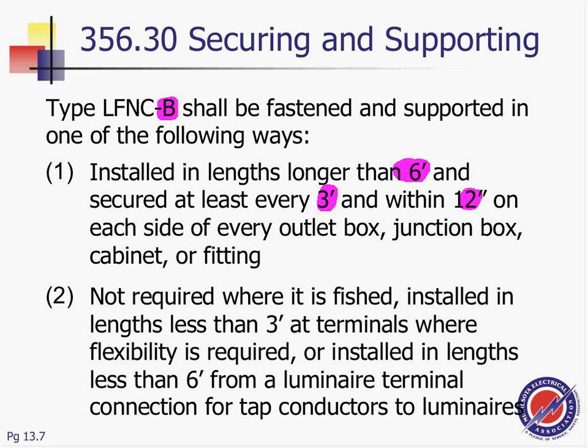Securing is not required where installed fished. If you fish it, installed in length less than 3 feet, no problem. Where flexibility is required, or installed in length 6 feet if it's tying to a luminaire. If you're having to feed a luminaire, no problem, up to 6 feet. If you need flexibility for equipment, 3 feet, no problem. Otherwise, if you're using this wiring method, every 3 feet and within 12 inches, you have to support the equipment. So 3 and 12, okay.